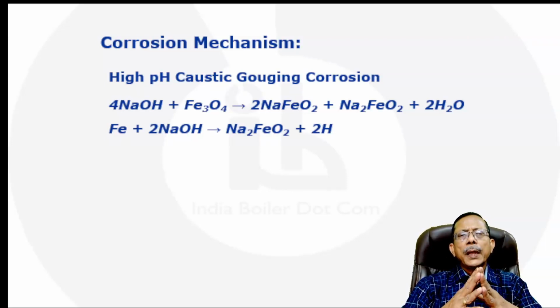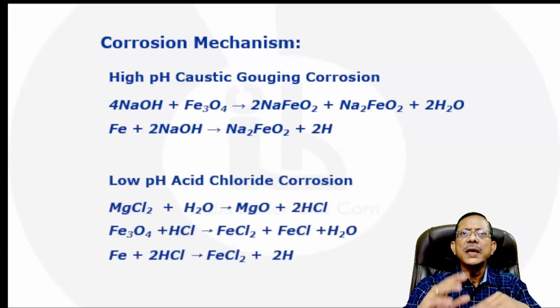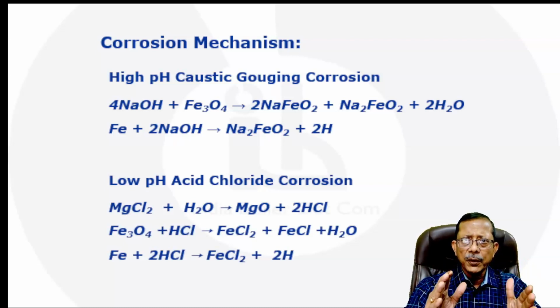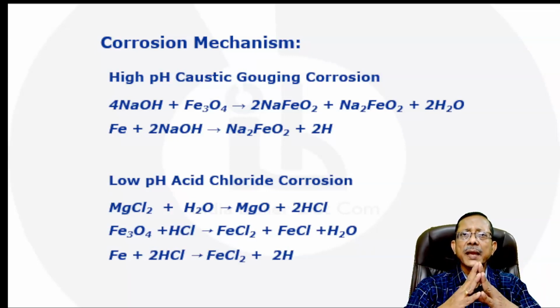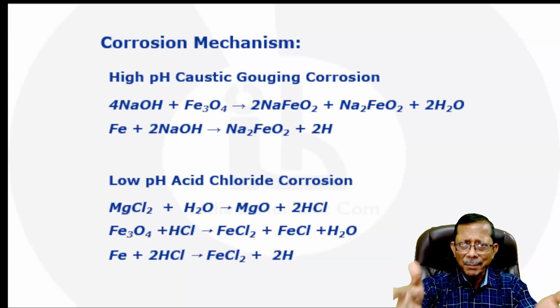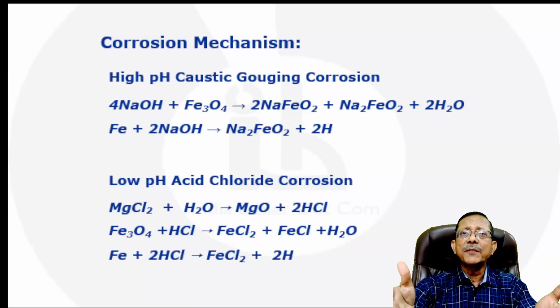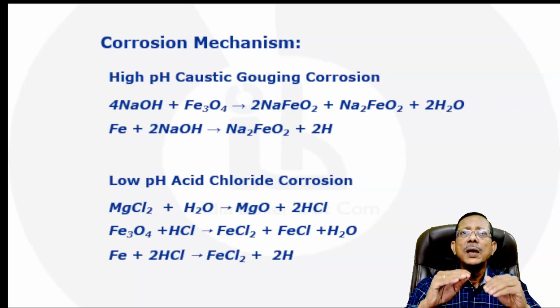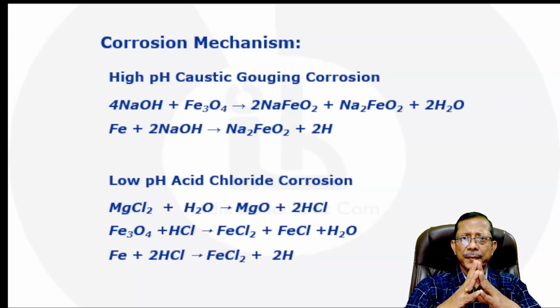Okay. Now, there is another corrosion mechanism that may lead to this embrittling problem, and that is the acidic chloride corrosion. Again, the location, water walls, below a porous deposit, below a film boiling, where there is a concentration increasing mechanism available. And if the concentration increasing mechanism leads to a very low pH because of the ionic imbalance, right, you might find that if there is chloride present in the boiler water at that time, the acidic chloride leads to acidic corrosion in the system, right?